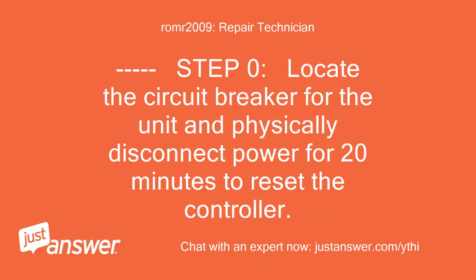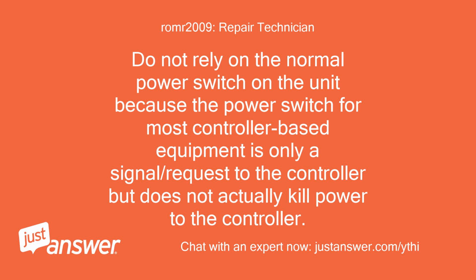Step 0. Locate the circuit breaker for the unit and physically disconnect power for 20 minutes to reset the controller. Do not rely on the normal power switch on the unit because the power switch for most controller-based equipment is only a signal/request to the controller but does not actually kill power to the controller.